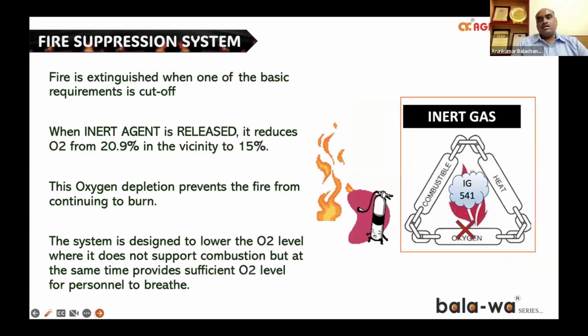So to fight, control, suppress and extinguish the fire, all we need to do is remove just one of the lines in this triangle. The combustible material is already there, which we cannot remove. So the only option is to remove either the heat or the oxygen. What the inert system does is reduce the oxygen from 20.9% to less than 15% in the area. This is an oxygen depletion method. By reducing the oxygen and replacing it with inert content, we are controlling and suppressing the fire using the inert system.